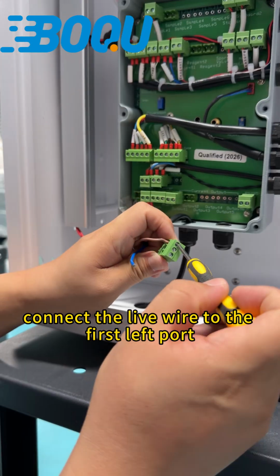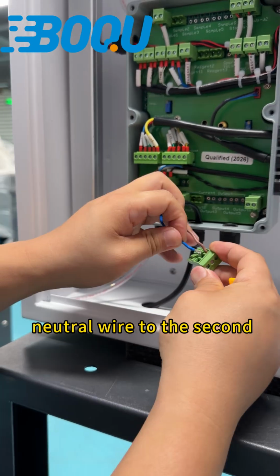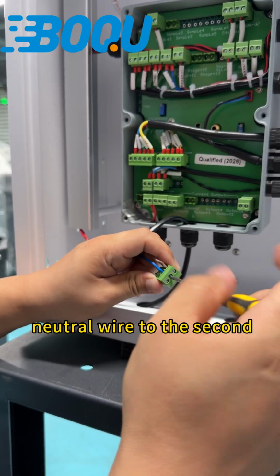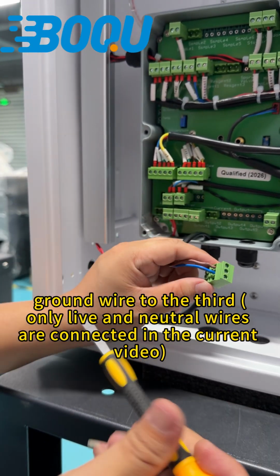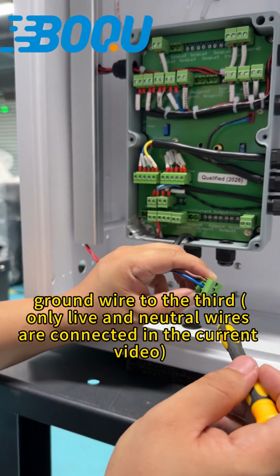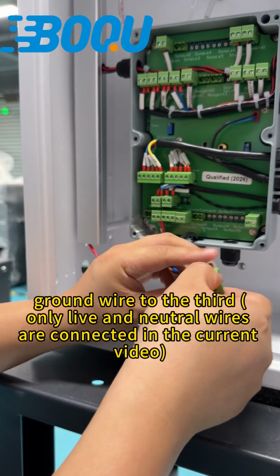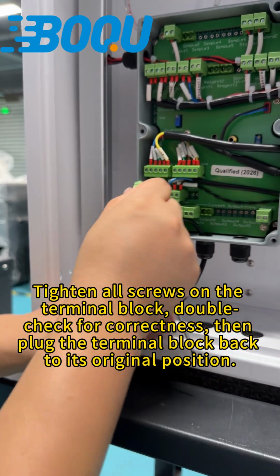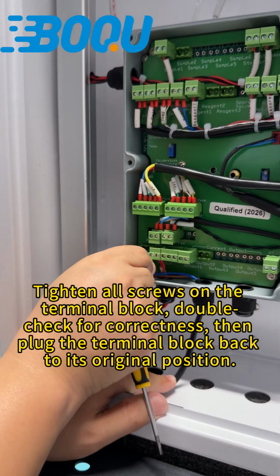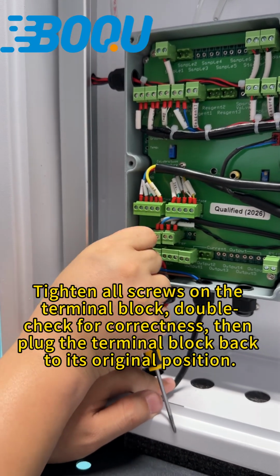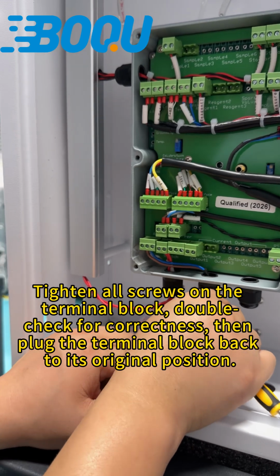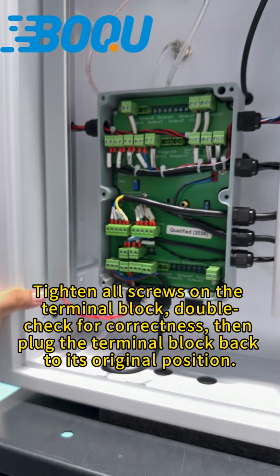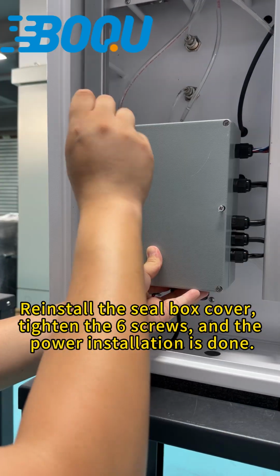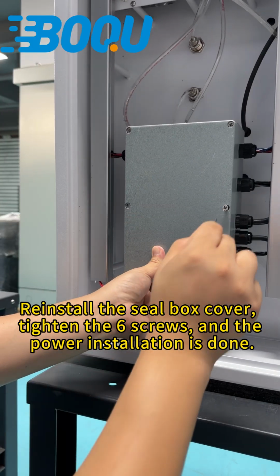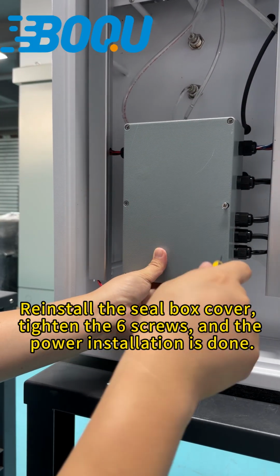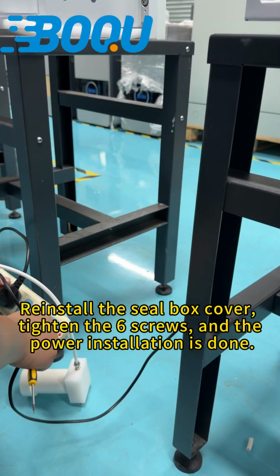Connect the live wire to the first left port, neutral wire to the second, ground wire to the third. Only live and neutral wires are connected in the current video. Tighten all screws on the terminal block. Double check for correctness, then plug the terminal block back to its original position. Reinstall the seal box cover. Tighten the 6 screws, and the power installation is done.